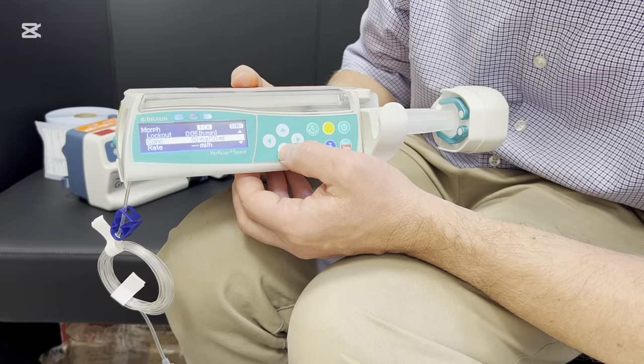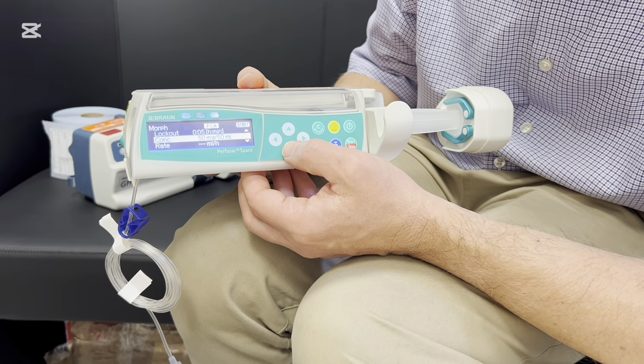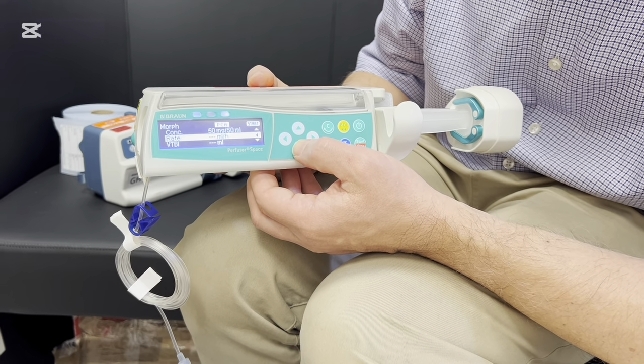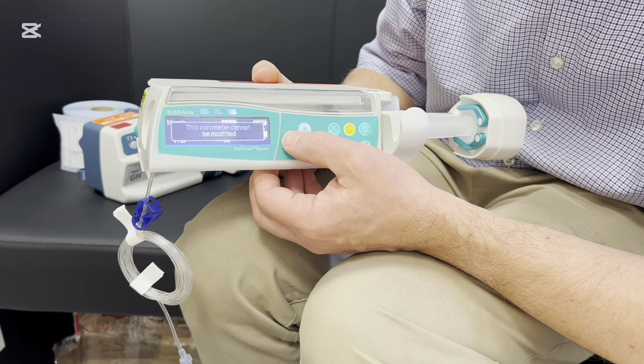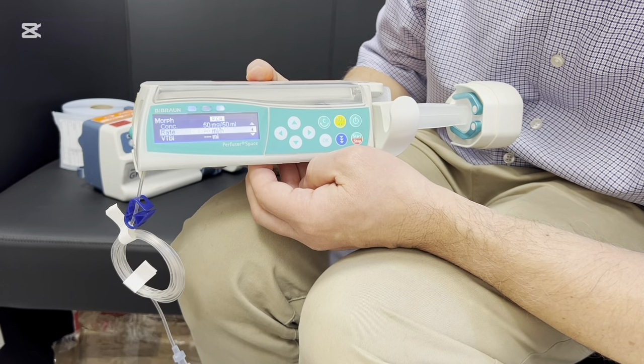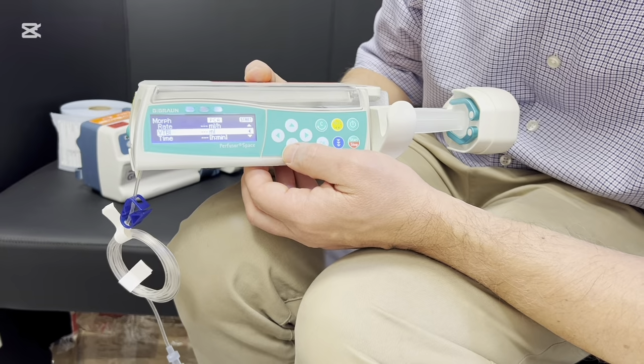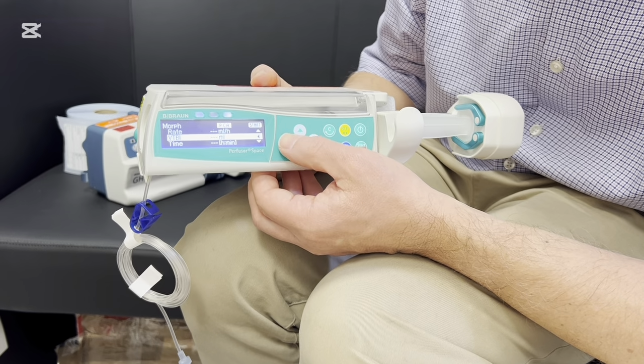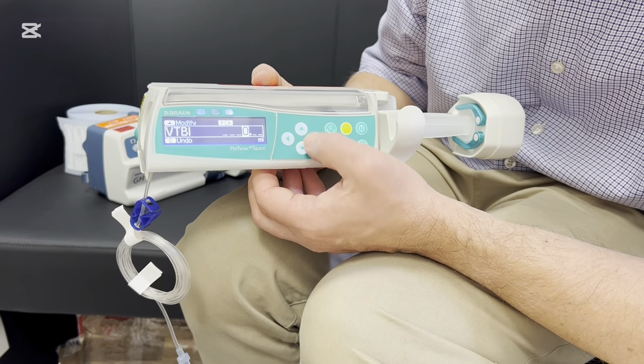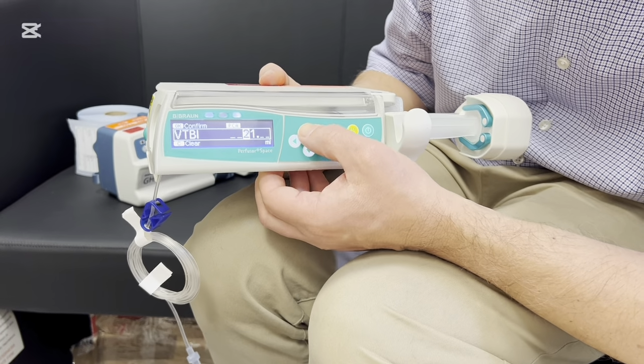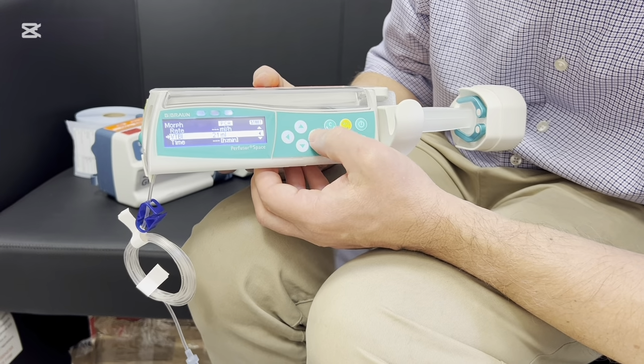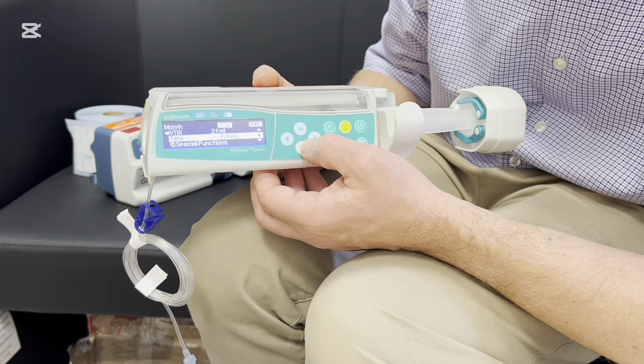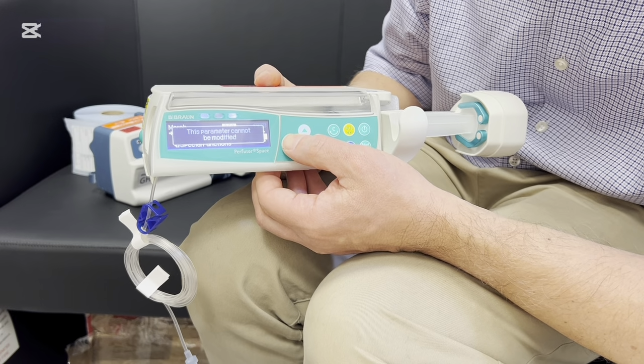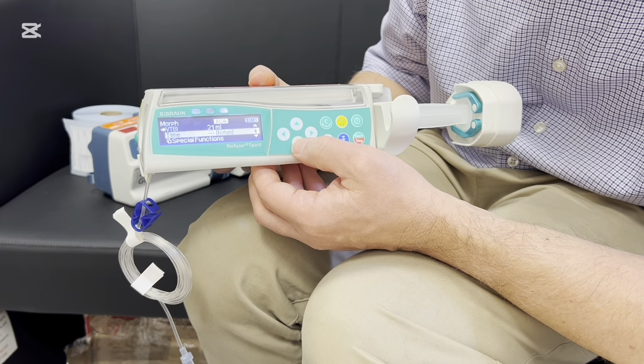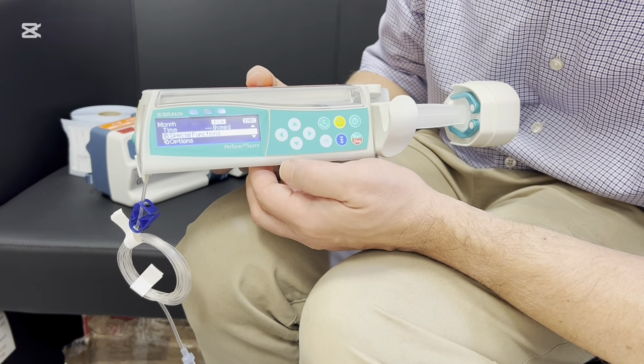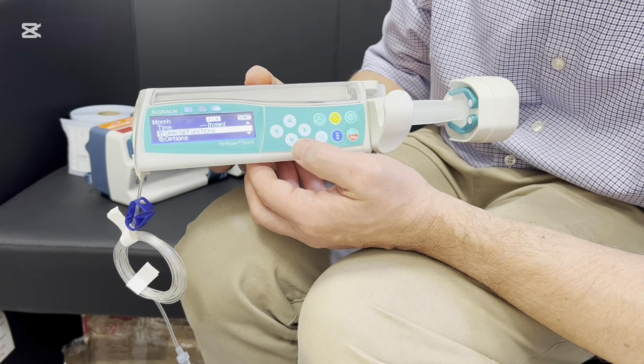It's 50 milligrams in 50 mils, so a 1 milligram per mil solution. I suspect we're not allowed to run a background infusion, we can try, but you can't do that. You can set a volume to be infused. I suspect it won't allow you to set a time period. So it has had a lot of its functionality stripped out of it to just make it a PCA pump.